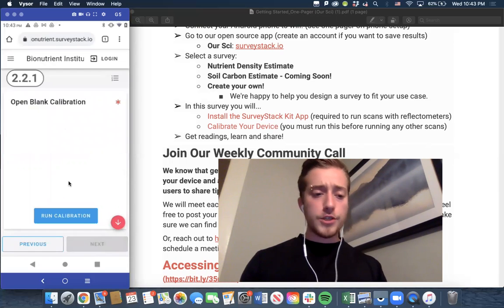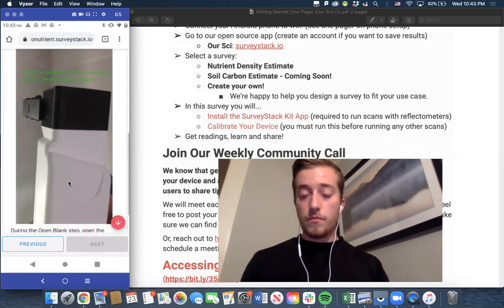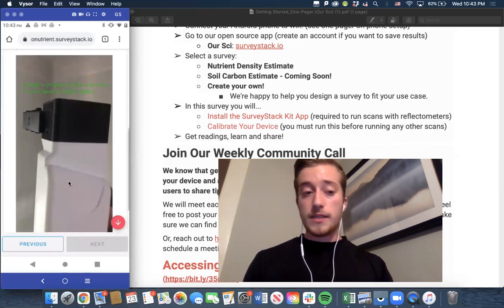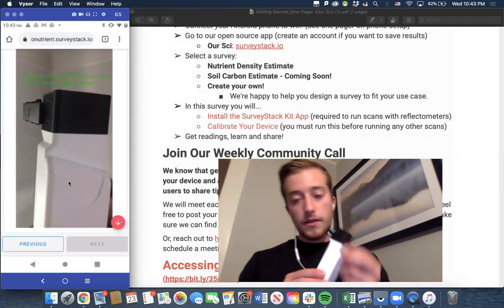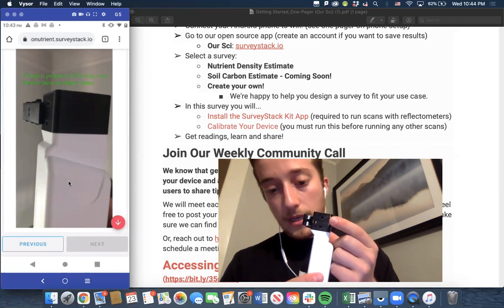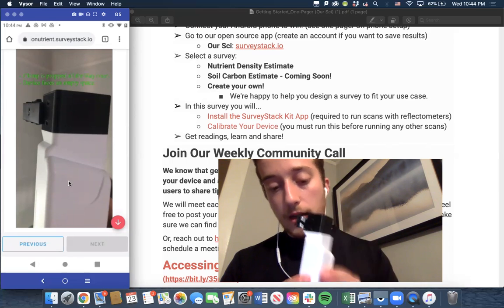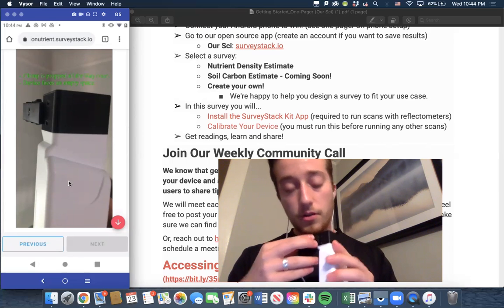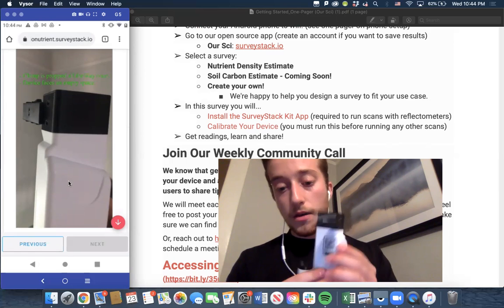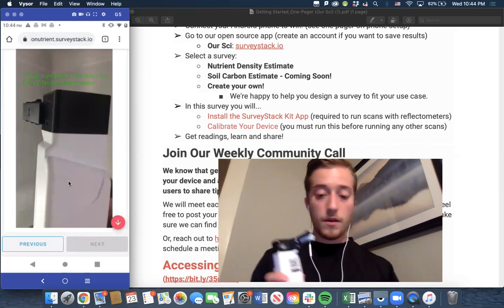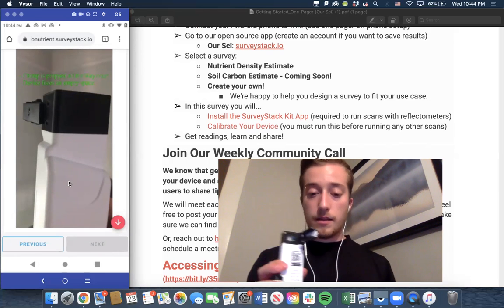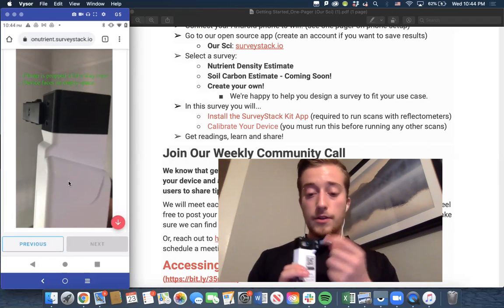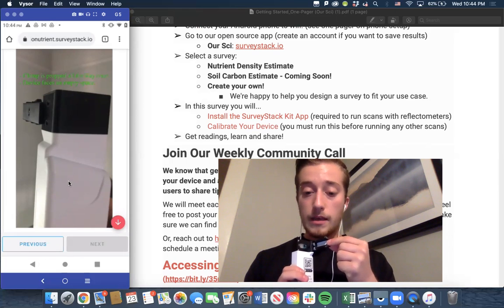My open blank calibration. There are instructions below if you scroll down for all of these steps. But my open blank, there's a little tab. It's difficult to see. It's this hole right here that allows you to prop your clamp open with a little hook. Again, you should clean that device surface, make sure it's clean, and you should clean the top of your clamp if there's anything in there.